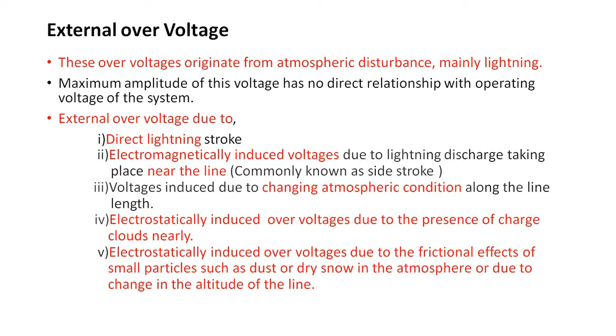External overvoltages are due to: first, direct lightning stroke. Second, electromagnetically induced voltages due to lightning discharge taking place near the line, commonly known as side stroke. Third, voltages induced due to changing atmospheric conditions along the line length. Fourth, electrostatically induced overvoltages due to the presence of charged clouds nearby. Fifth, electrostatically induced overvoltages due to frictional effects of small particles such as dust or dry snow in the atmosphere, or due to the change in the altitude of the line.